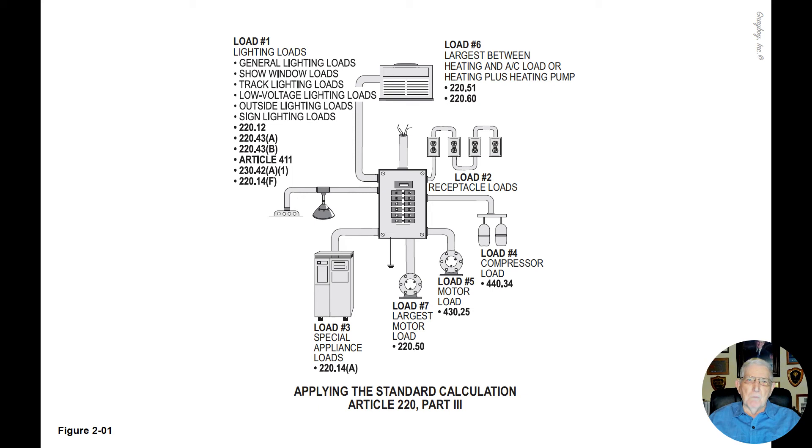Load 5 would deal with motor loads and we also take those motor loads at 100 percent of the full load current rating, which 430.6A of the code refers you to table 430.250 based upon voltage and horsepower. The motor you would pick up the full load current ratings for three-phase motors.